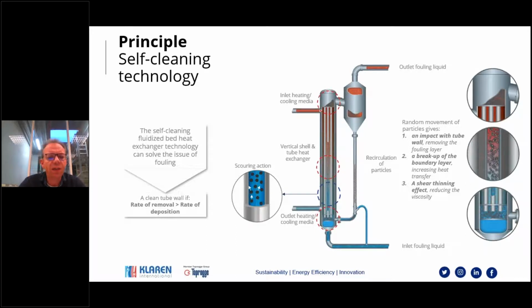So by having this fluidized bed cleaning system in place, as long as we remove the layer faster than it can develop, the net effect is that the tube wall remains clean. And this is in fact exactly what we want, because we see that in many cases in industry we have fouling of a heat exchanger, meaning we have the formation of an insulating layer on the heat exchange surface, and this gives rise to all kinds of cost, leads to reduced capacity, cleaning cost, more energy. So a lot of unwanted effects that we can solve with adapting this technology.